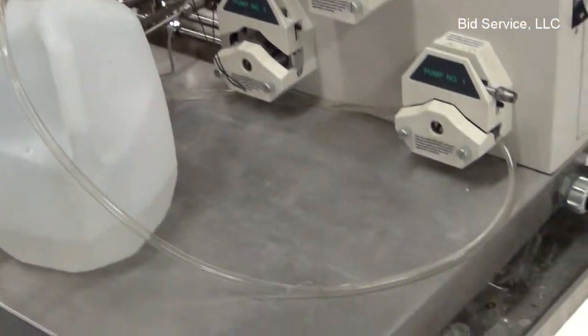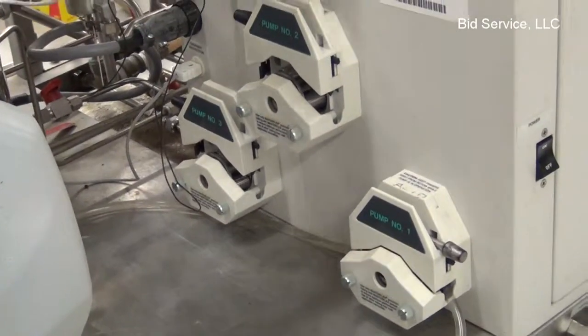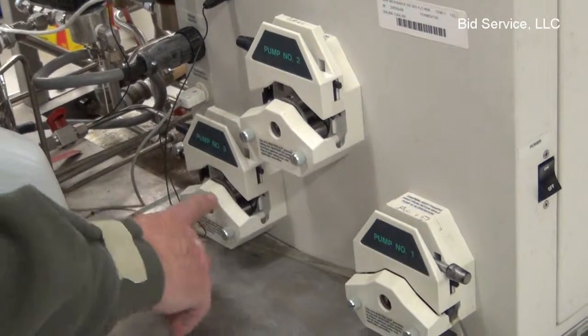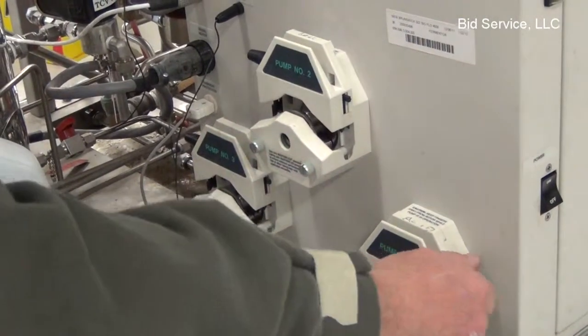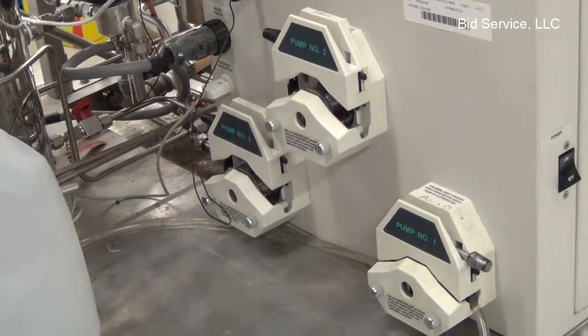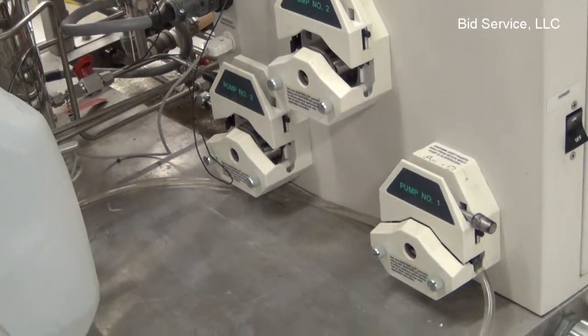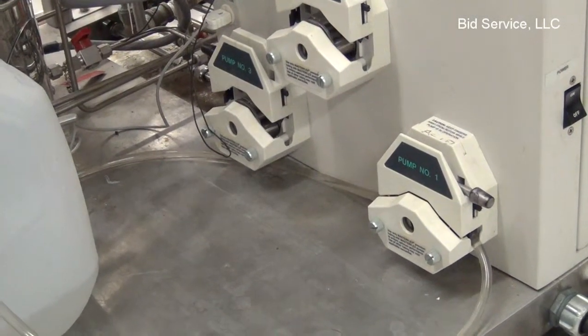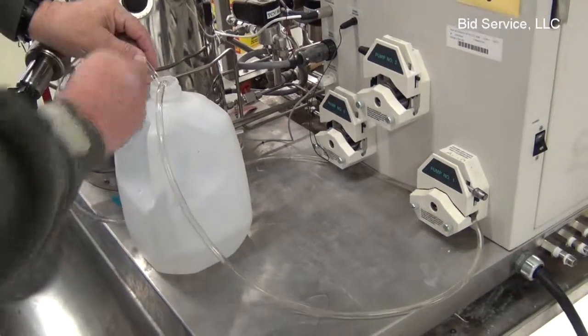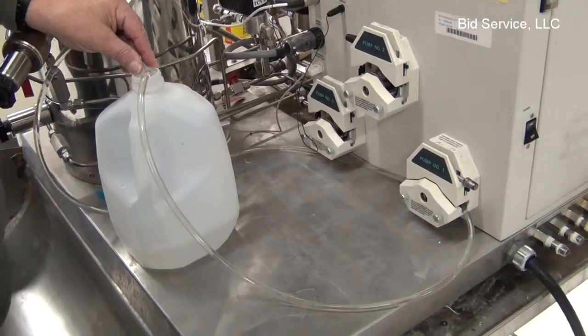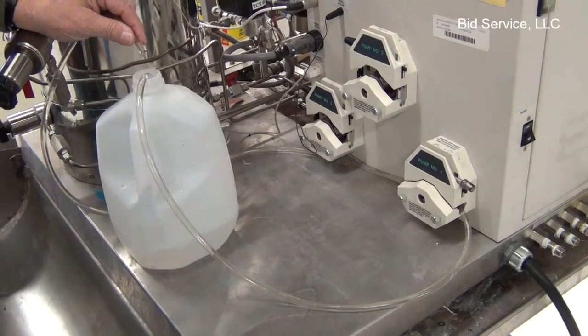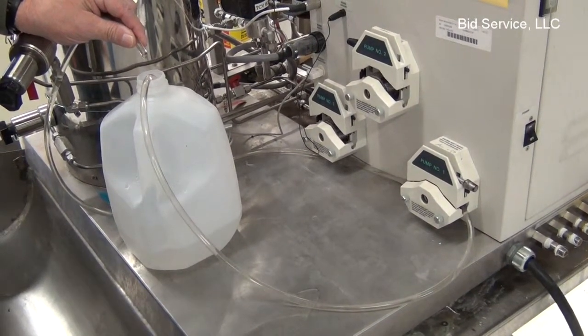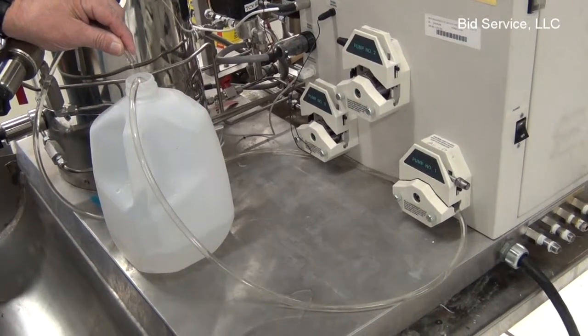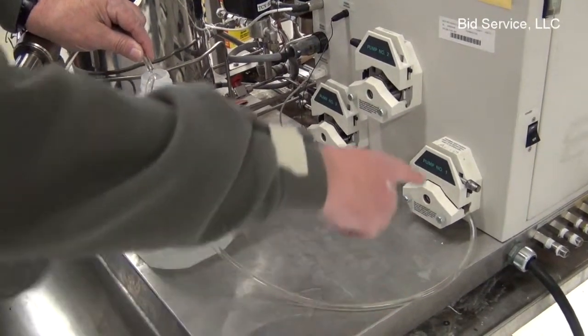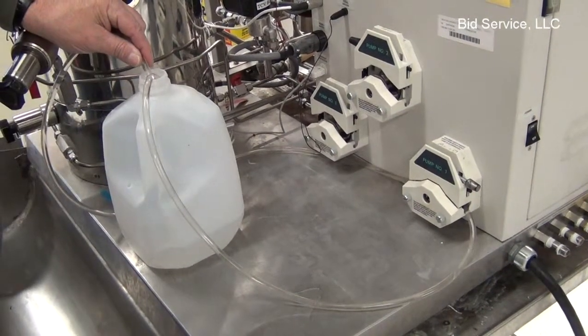The last thing I want to show you down here is the peristaltic pumps. There are 3 of them. I've gone to that page of the gauges, and as you can see, they're all moving. The peristaltic pump for this system is not a speed control. It is a tubing control device in conjunction with time. As you can see there, we're getting flow rate through this tube, and I'm just feeding it through the pump and back in just to show you how it works.